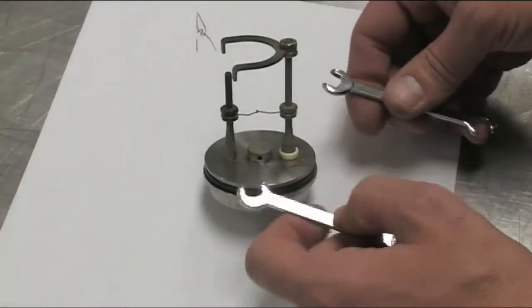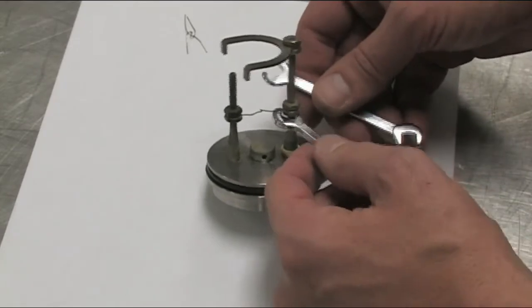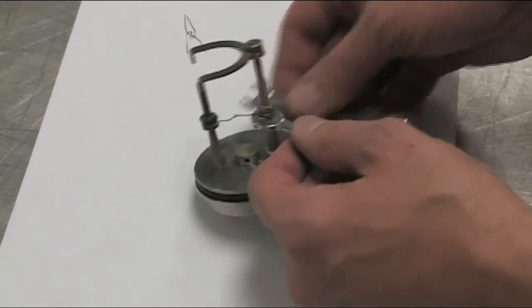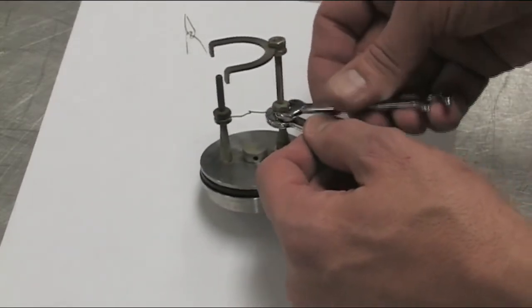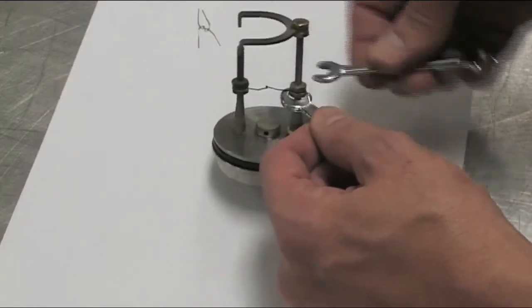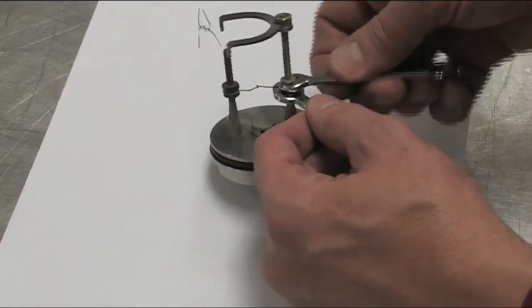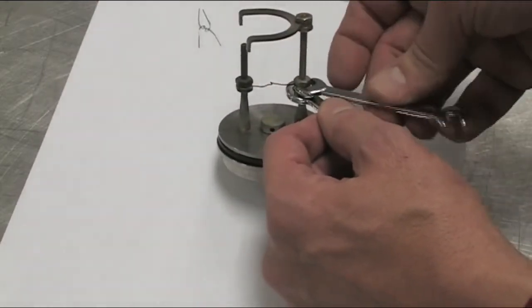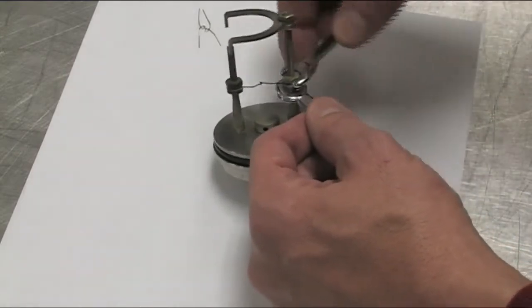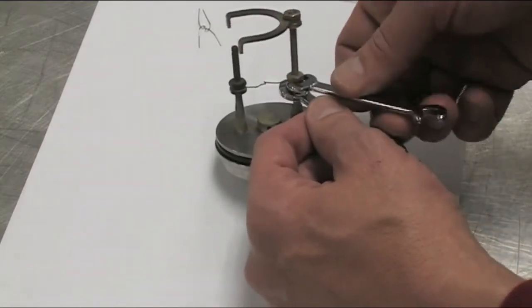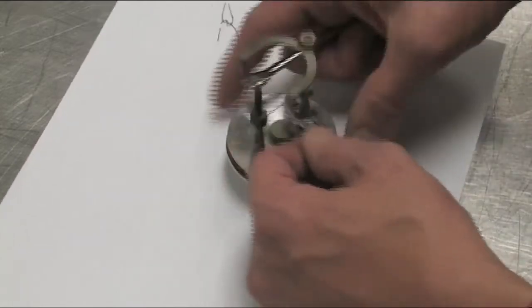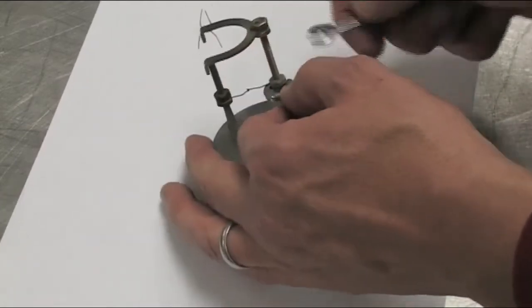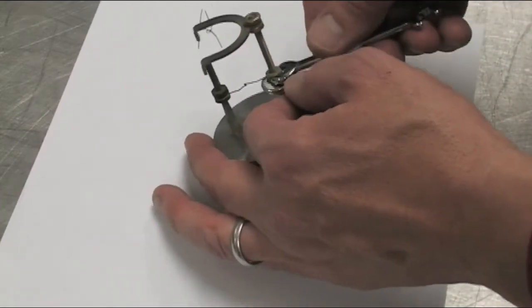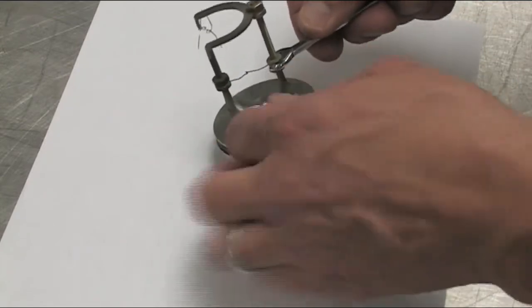What you have to do next is remove the old ignition wire. You'll need 2 5/16 inch wrenches, one on each side, to loosen the screws. The shorter electrode you may want to carefully inspect. That electrode may need to be replaced at the same time as the igniter wire, depending on the condition of the electrode.